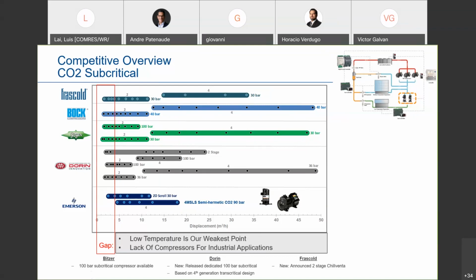It's a high standstill pressure system. So, you either want a low side, low temp pressure relief blowing off if the system's off for an hour for whatever reason. So what they'll do is they'll design the whole system for much higher standstill pressure, the piping, the evaporators, everything. So if, let's say, it's a 90 bar standstill, which is, I forget the pressure, I think it's 1,305 pounds, then your pressure release would be at 1,305. That means your compressor needs to be able to handle it, as well as your suction piping and your evaporator.